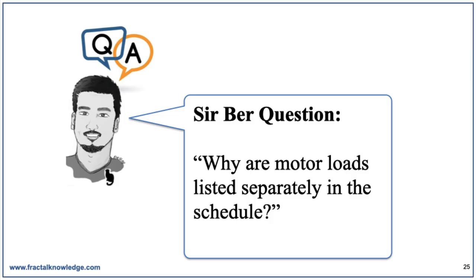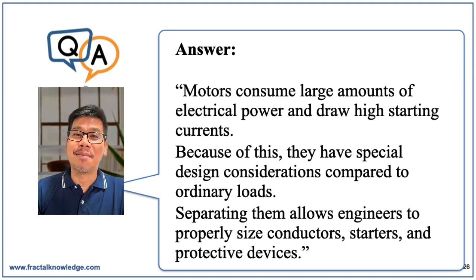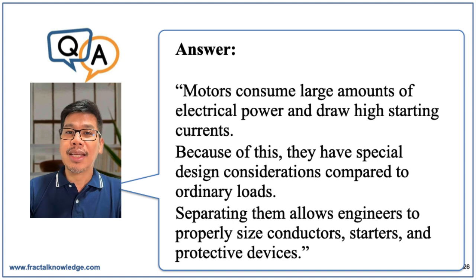Tanong, why are motor loads listed separately in the schedule of load? So, motors consume a large amount of electrical power and draw high starting currents. Minsan magti-trip yan because of in-rush current. Hindi mo na i-design yung protection devices mo. Because of this, they have special design considerations compared to ordinary loads like lighting and mga outlets. Separating them allows engineers and electricians to properly size conductors, starters, and protective devices.